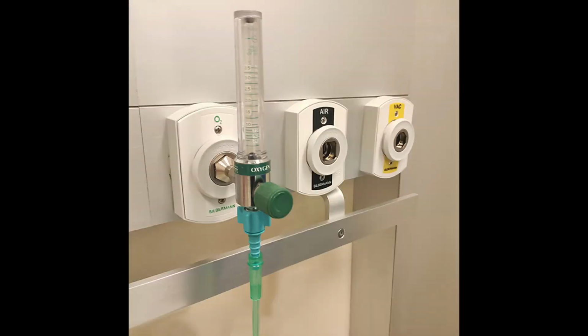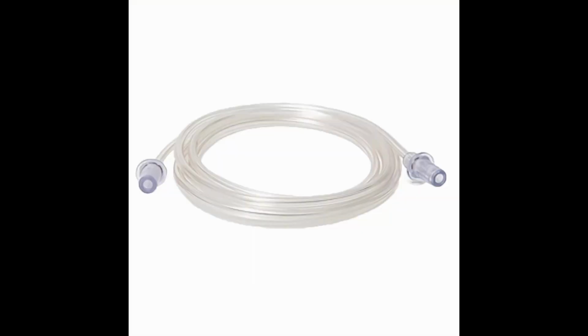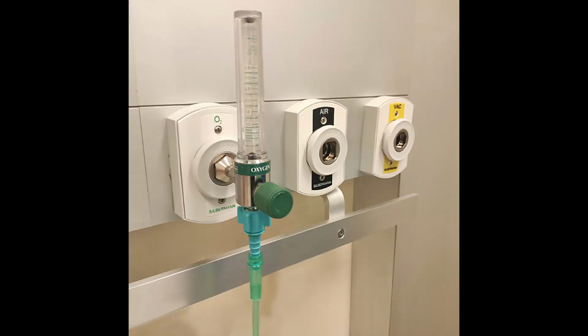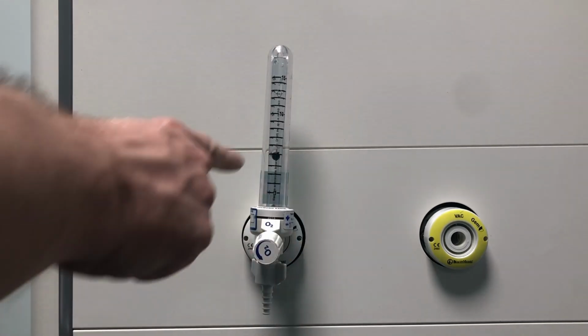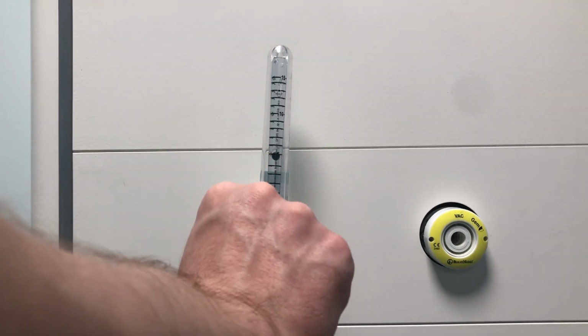Now, to connect the green O2 tubing, now it's not specifically green, the tips used to be green. You may find that it is clear now. Connect the O2 tubing over the tubing nipple outlet and adjust the flow meter to the requisite flow. Ensure all connections are tight and leak free, ensuring that the ball is cut through by the line directly through the middle at the prescribed rate.